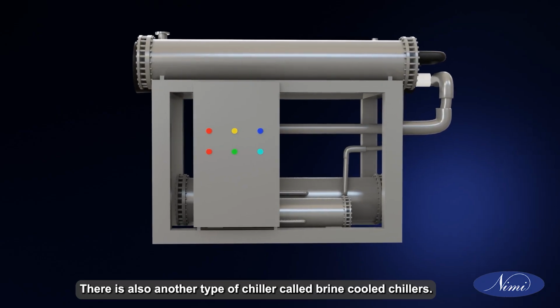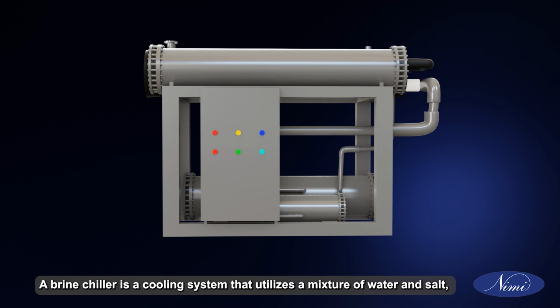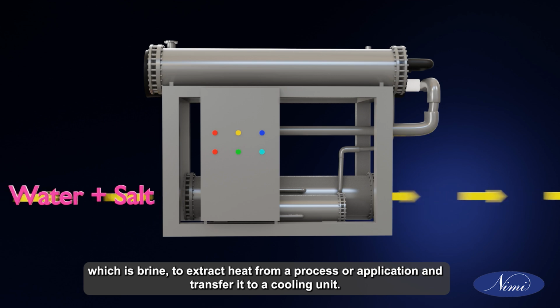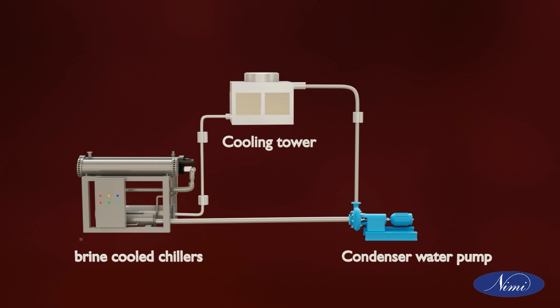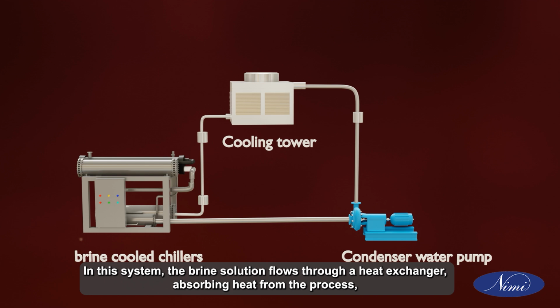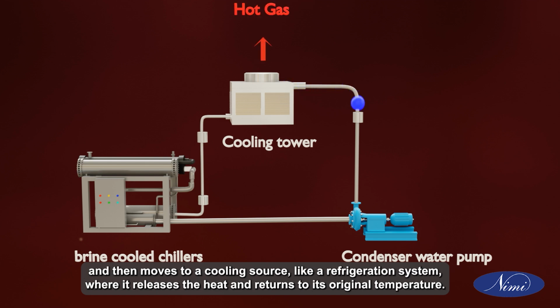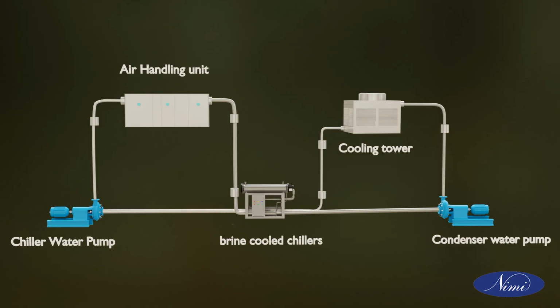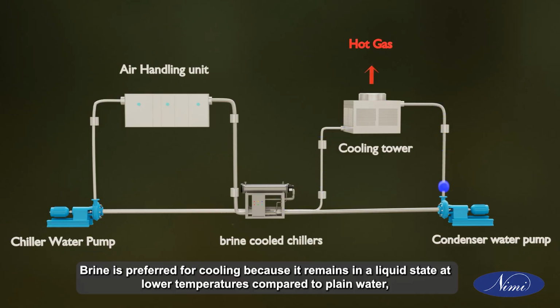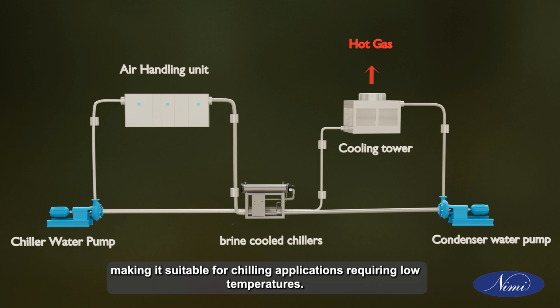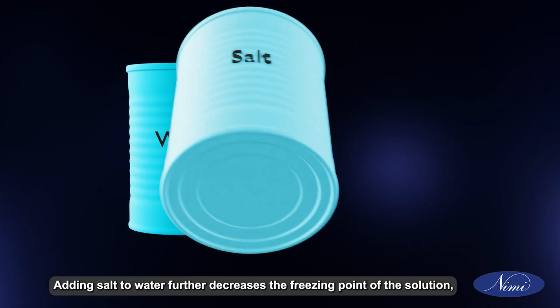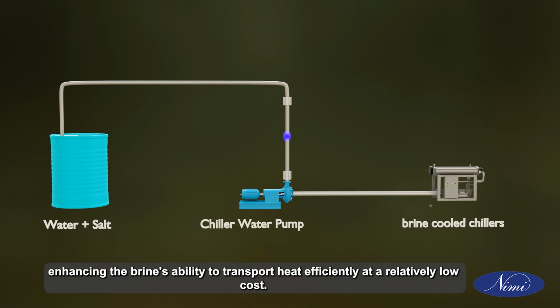There is also another type of chiller called brine-cooled chillers. A brine chiller is a cooling system that utilizes a mixture of water and salt, which is brine, to extract heat from a process or application and transfer it to a cooling unit. In this system, the brine solution flows through a heat exchanger, absorbing heat from the process, and then moves to a cooling source, like a refrigeration system, where it releases the heat and returns to its original temperature. Brine is preferred for cooling because it remains in a liquid state at lower temperatures compared to plain water, making it suitable for chilling applications requiring low temperatures. Adding salt to water further decreases the freezing point of the solution, enhancing the brine's ability to transport heat efficiently at a relatively low cost.